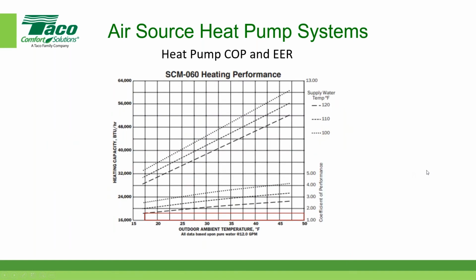Okay, this is really the same chart, so I want to skip over that. This is the heating. Again, this is what we talked about a minute ago. We calculated 1.59, and there's 15 ambient temperature. If you'll notice, this line here represents the 120 supply water temperature. So that means it has a capacity at around, that's 15, that's 20, that's about 17, a little more than halfway between the two, 17.5, but we'll use that. We come up here, you can see that's 24,000, that's 28,000. That should be 8 between the two. That means a little bit above 28,000, the same number that we used before. Again, graphically, you can see what happens. As the ambient temperature begins to drop, the COP also begins to drop. But look what happens, this is the opposite end.